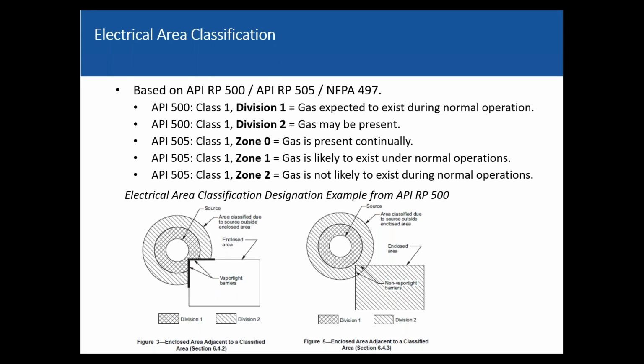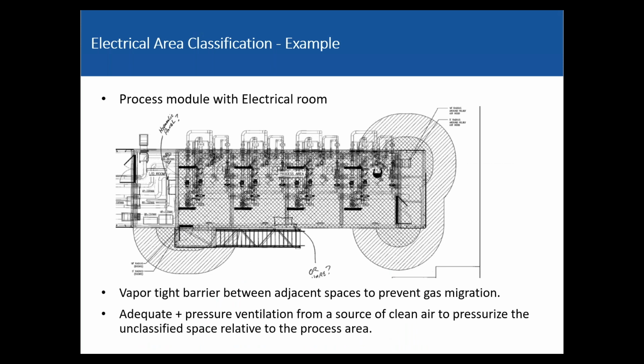All right, so if we have these gas boundaries, a hazardous area, things go boom. We have a control room with arcing and sparking equipment. We want to protect that, so we put in a vapor tight barrier, and we can say, oh, we're isolated. Don't. We have to extend, because this is an enclosed module, we have to extend the hazardous area into that module, which is what we don't want to do. That causes you to have to buy a whole bunch of really expensive explosion-proof or intrinsically safe electrical equipment. There's stuff that you can't even get. And if you have questions as I'm talking, just shout them out, raise your hand, whatever. Okay, so that was kind of the generic.